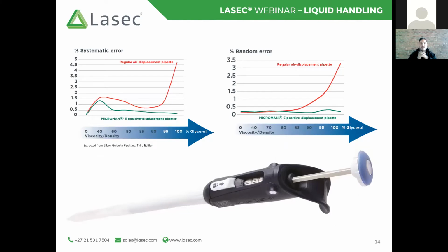So just as an illustration with glycerol, I want to show you the systematic errors and random errors that you could experience using either an air displacement pipette or a positive displacement pipette. We will discuss systematic error and random error at the end of this webinar when we start discussing performance attributes. But for this case, as you can see, with increasing viscosity from 0 to 100%, if you are doing this with a regular air displacement pipette, from the mid to high viscosities you will see a drastic increase in the systematic error and random error of your results. However, with a positive displacement pipette, although there is slight deviation, you are able to maintain a relatively constant systematic and random error, regardless of the viscosity of the solution.